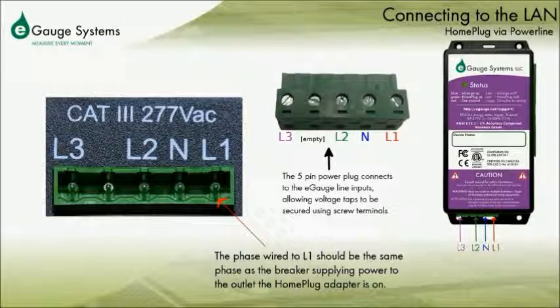The eGauge has 3 voltage inputs. Each voltage input, labeled L1, L2, and L3, reads a single phase of the electrical system being monitored. The L1 input is for home plug communication as well as power and one of the voltage references, so the outlet the home plug adapter is connected to will also have to be on the same phase as the one wired into L1 of the eGauge.